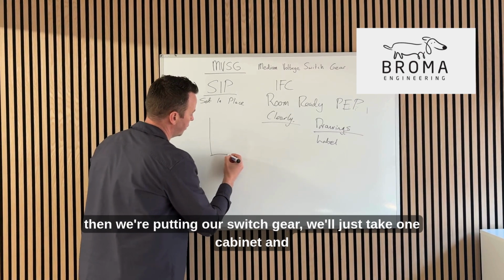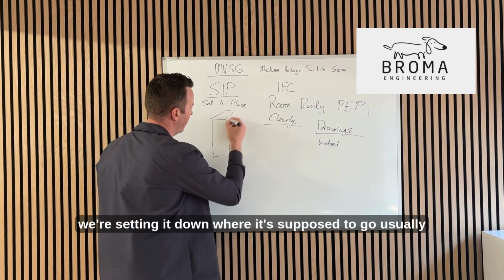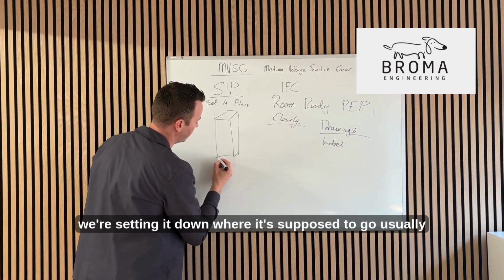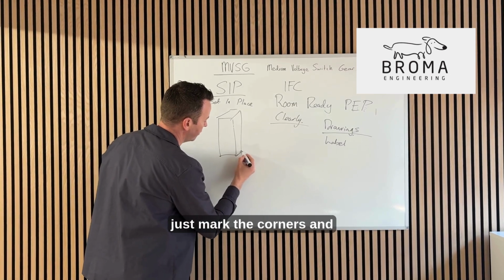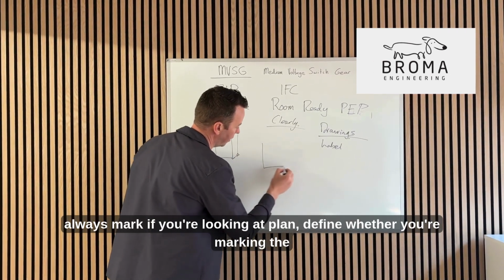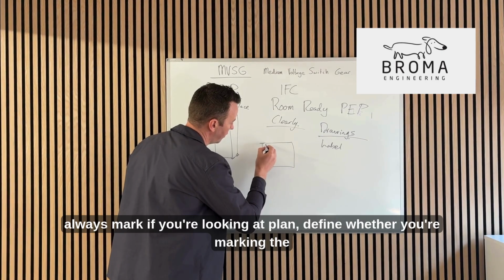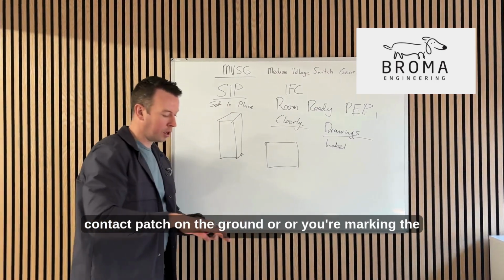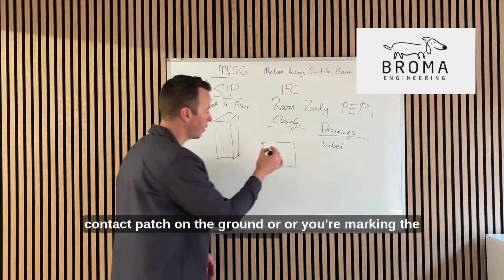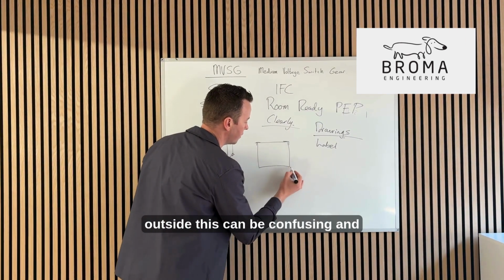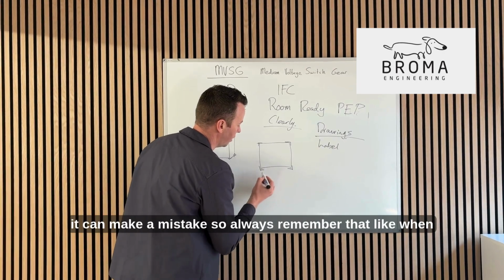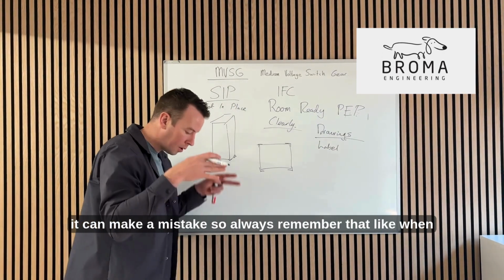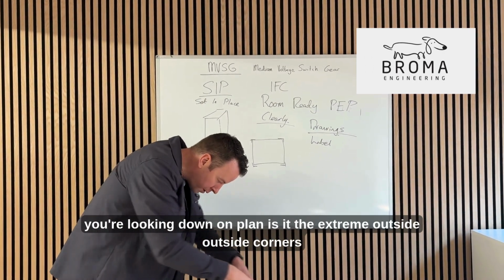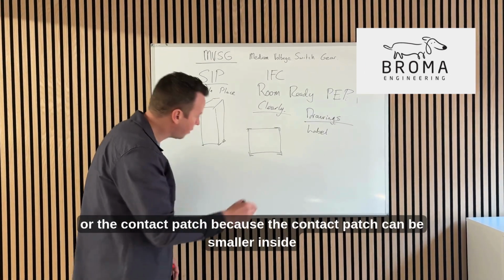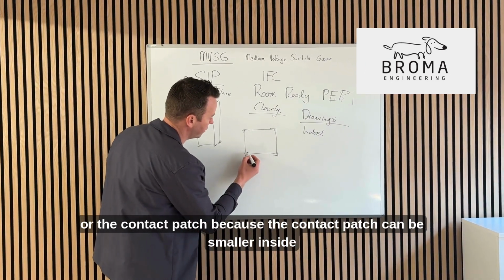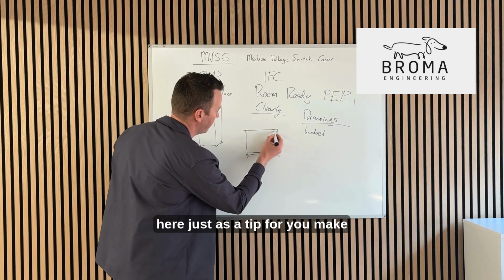And then we're putting our switchgear. We'll just take one cabinet and we're setting it down where it's supposed to go. We usually just mark the corners, and always mark, if you're looking at plan, define whether you're marking the contact patch on the ground or you're marking the extreme outside. This can be confusing and it can make a mistake. So always remember that, when you're looking down on plan, is it the extreme outside corners or the contact patch? Because the contact patch can be smaller inside here.